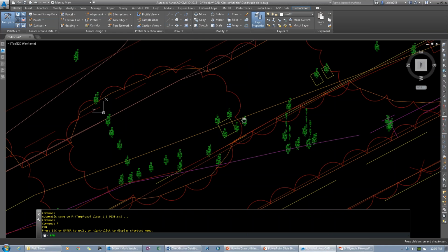Okay, so what's the minimum radius for a distribution line? 25 feet. Why do I get lines drawn at angle points? Okay, I'll get a 90-degree drawn, and it'll be in the drawing that way. And I'm going, okay, well, there should be a radius there. Okay, what's the minimum radius for a telephone line? 15 feet. Okay, for a house service, it's 5 feet.